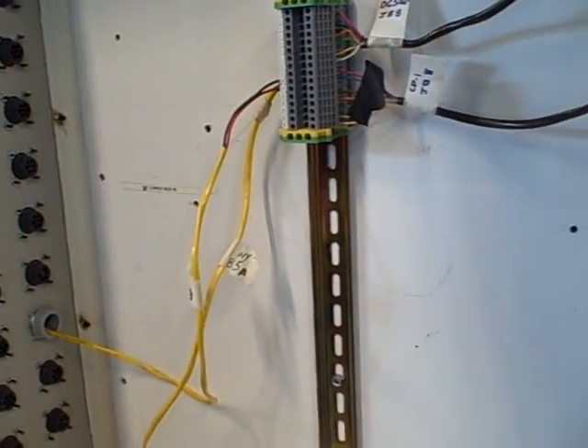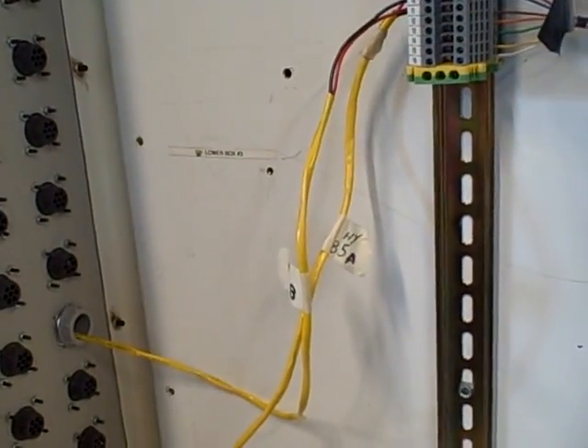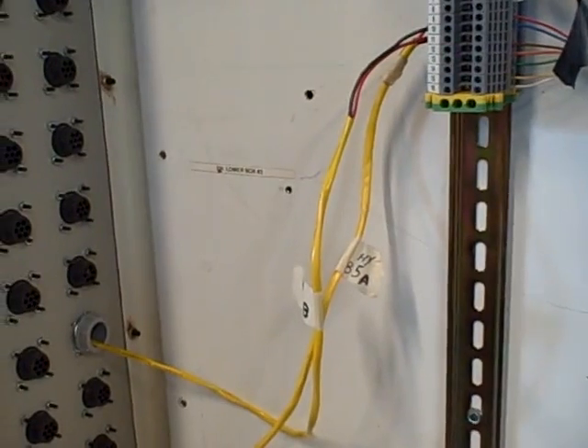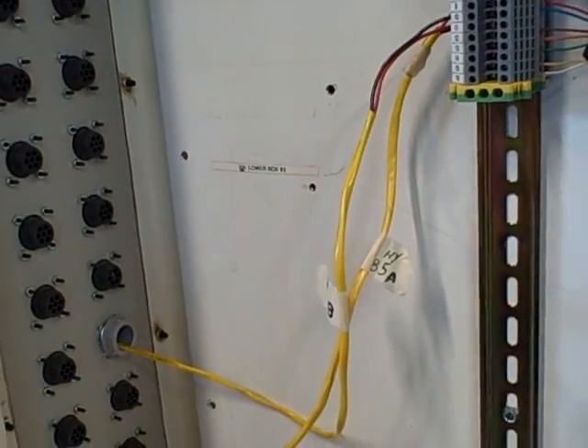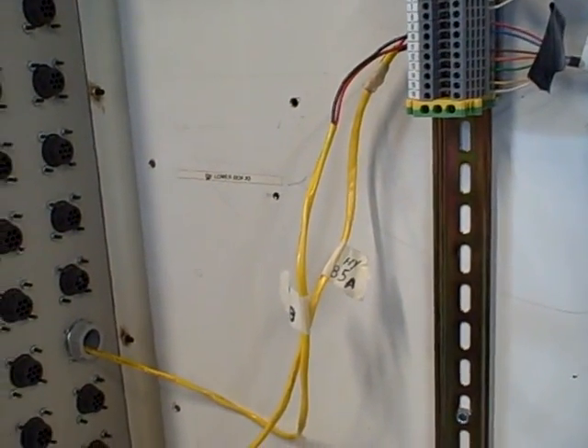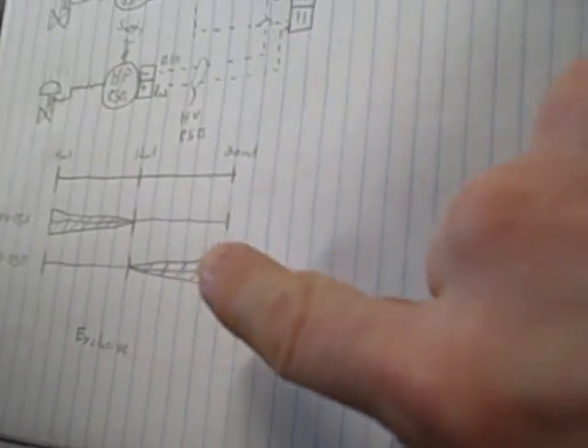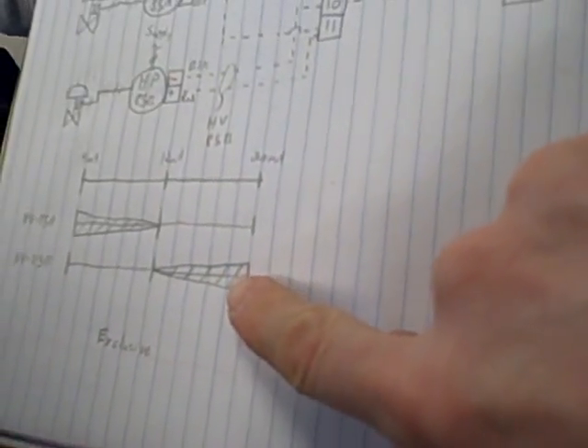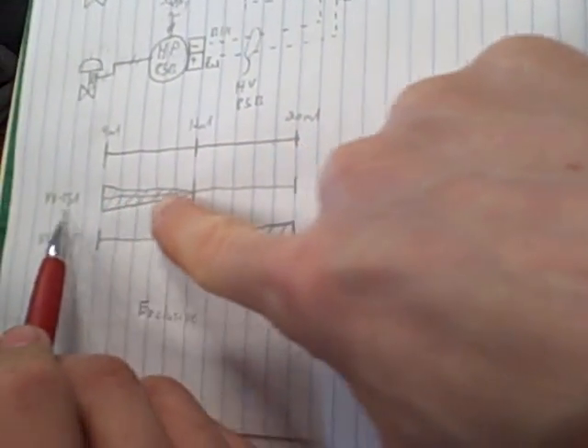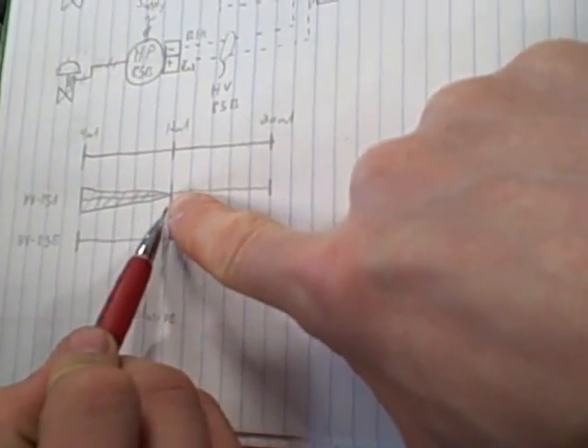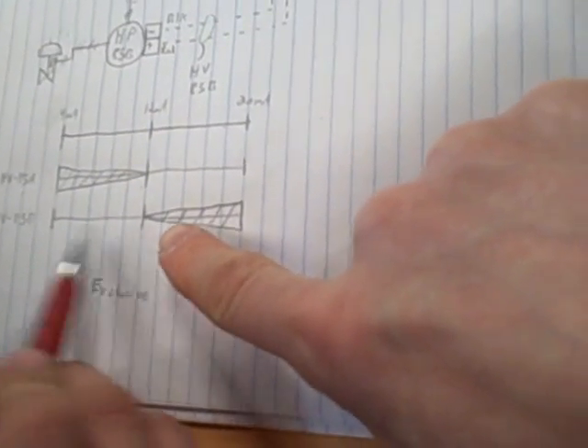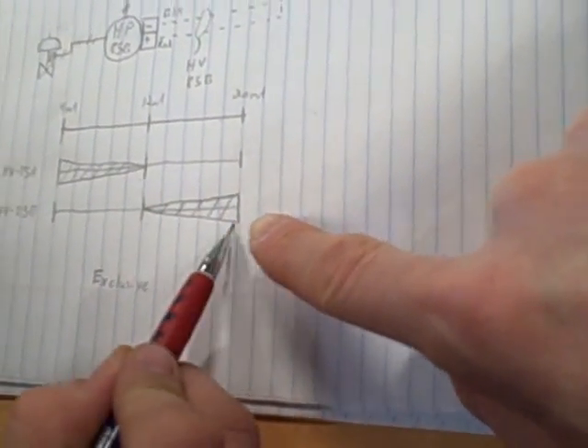One final step as we're checking these diagrams. I want to make sure that the split ranging is clearly and unambiguously denoted on all the diagrams. So that anyone looking here understands how the split ranging is done. Now taking a look at this diagram here that Ken's got, I see it's an exclusive split range. Looks like HV85A handles the lower end from 4 to 12 milliamps. HV85B handles the upper end from 12 to 20. Is that in agreement with everyone? Yes. Okay.